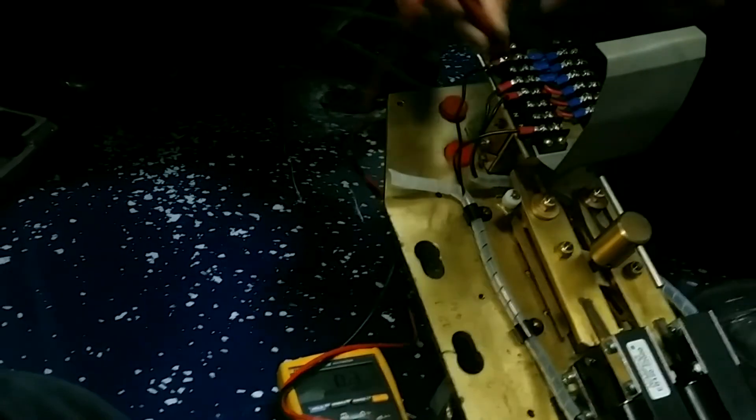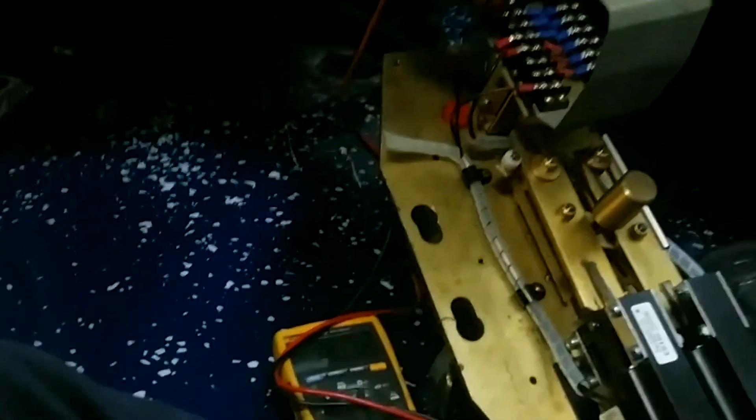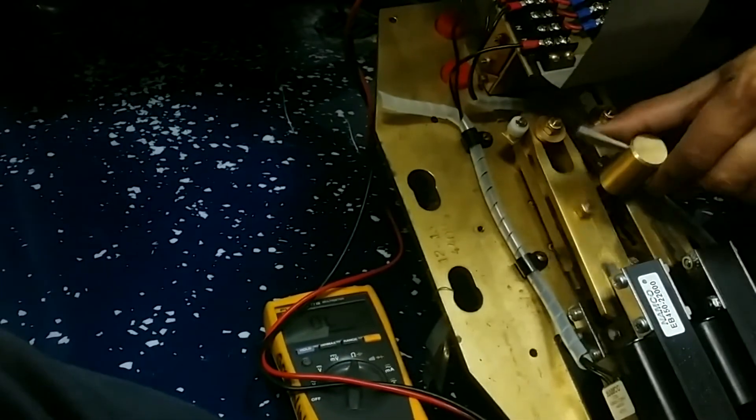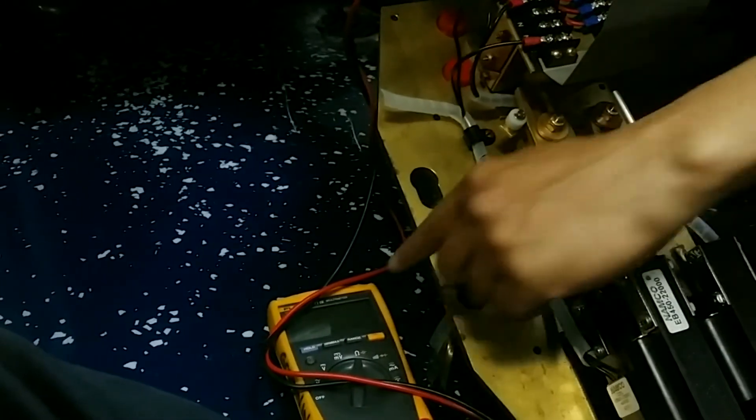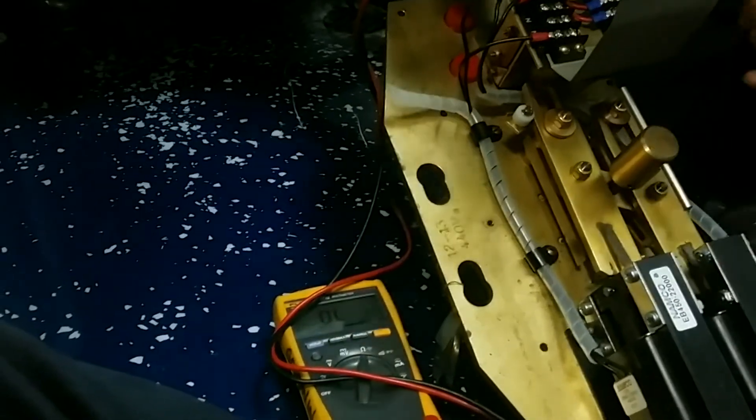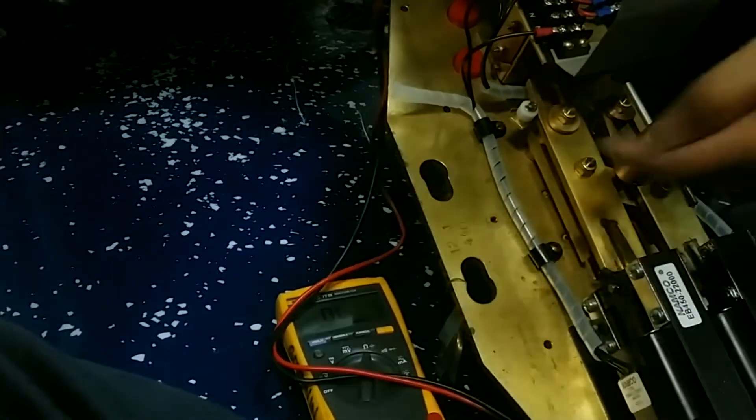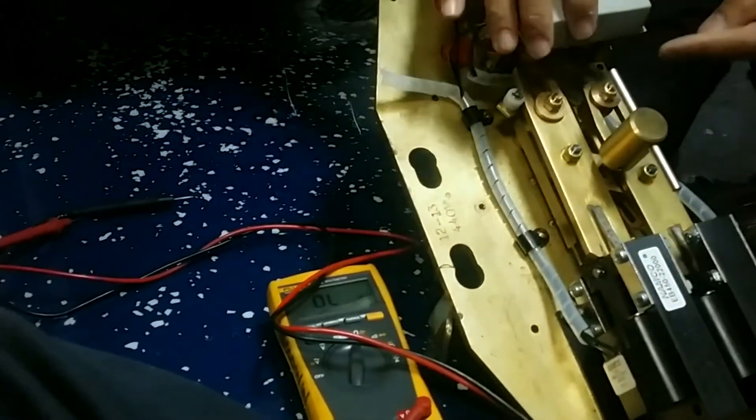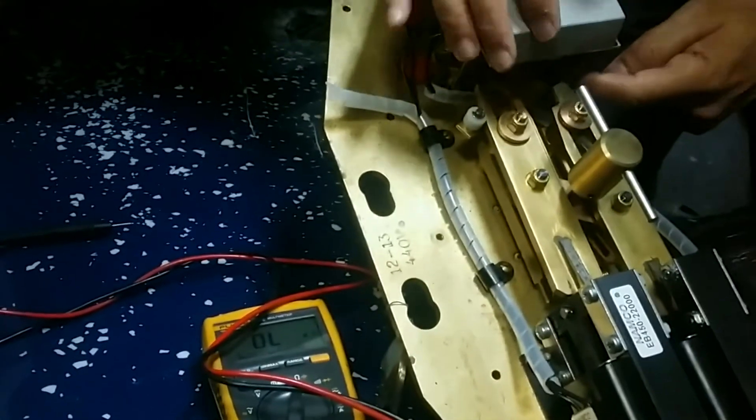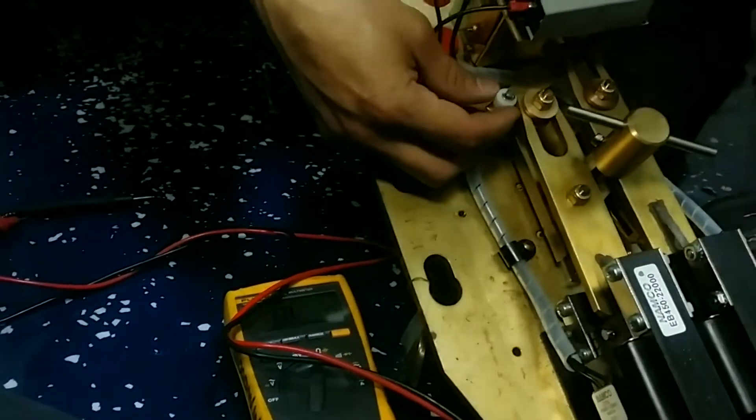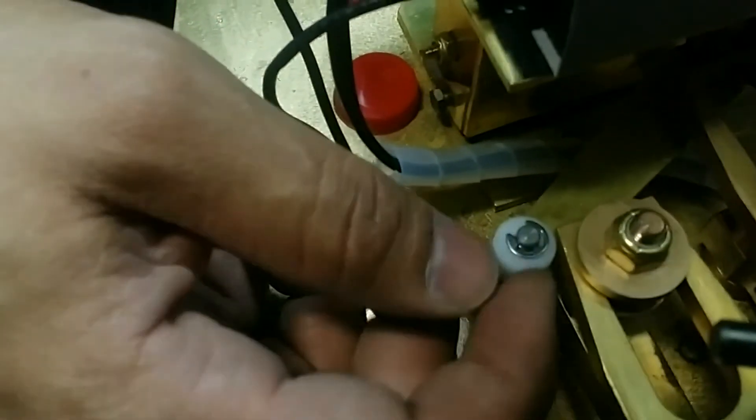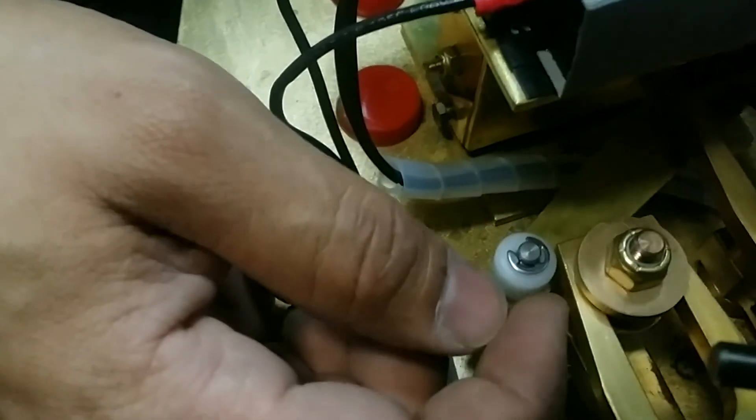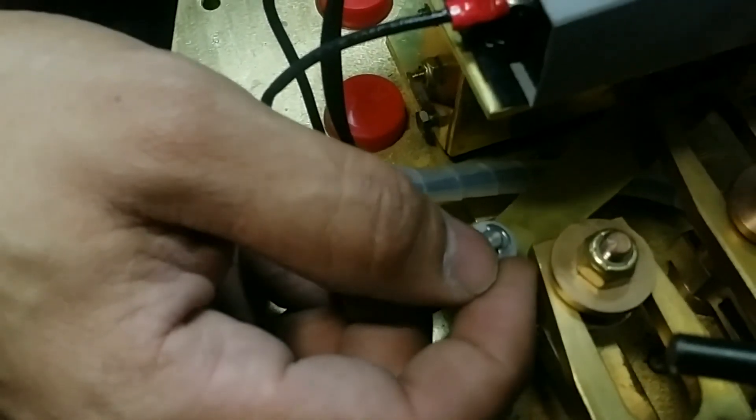This is a brand new valve. I got my normally closed, and then common, and as I put it there, and as I'm shifting the valve, right now it's working, but it's not. See how the multimeter cannot make its decision? That's because this lever here is not fully activated. So we're going to have to adjust this valve, we're going to have to take this little allen wrench here, so that this will engage a little early. In the video, you might be able to hear the microswitches actually engaging. It's very important that all three microswitches, three different clicks, actually hear...